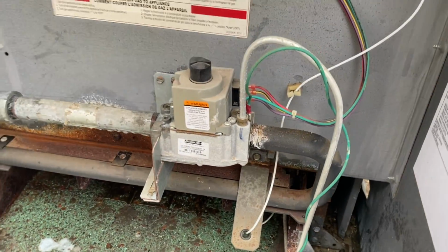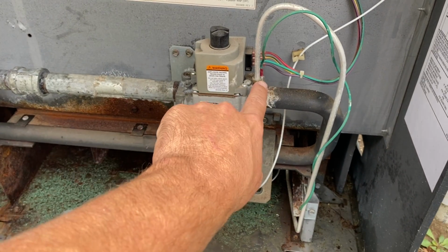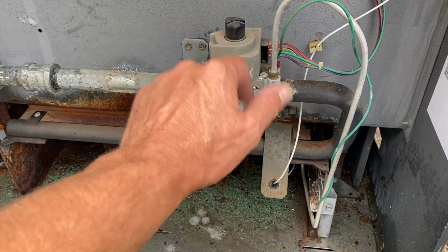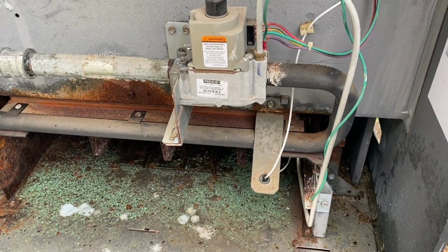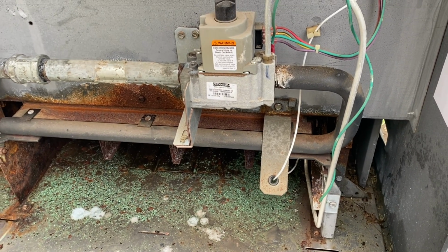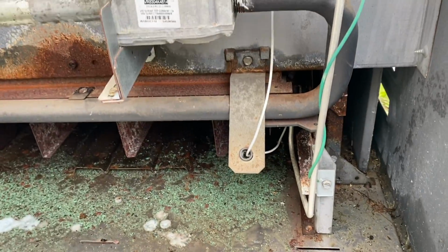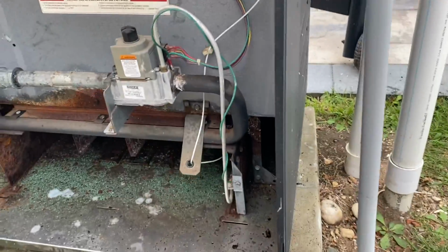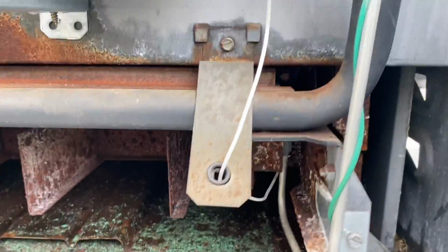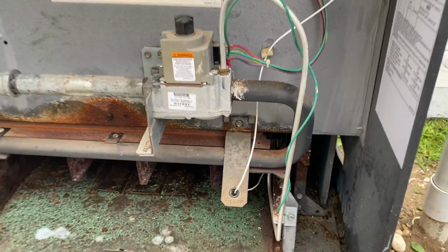The thermocouple, by the way. It's a good wrench to have. It does this on one side, and it does the thermocouple on the other. What size is, you don't know? I don't know off the top of my head, but I have it in the big tool bag. It's a good wrench. I have flame. See it? It's not sensing flame.